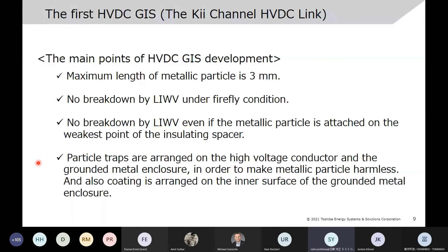And next is outline of the second HVDC GIS development. The picture shows the second HVDC GIS in 2019 at Hokuto converter station of the new Hokkaido Honshu HVDC link. In this link, a symmetrical monopole system is applied. And the point is, insulation material of this link was changed from that of the Kii Channel HVDC link. And also the coating material on the inner surface of the grounded enclosure was changed. So at this moment, it is difficult for metallic particle to lift off.